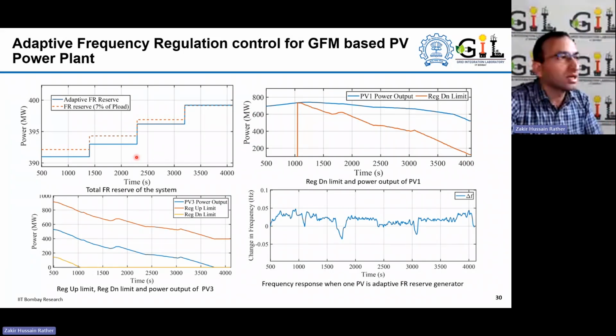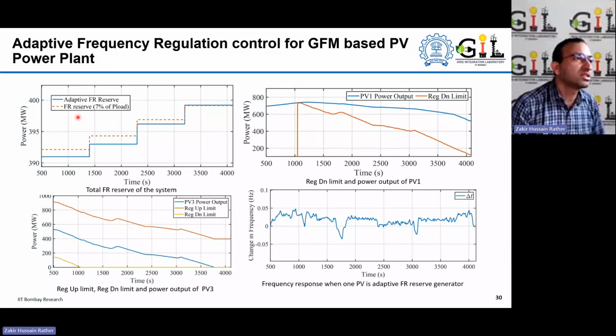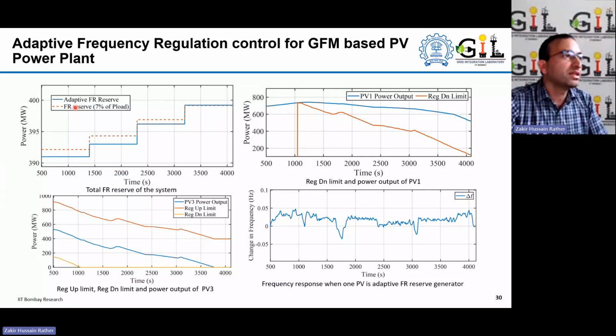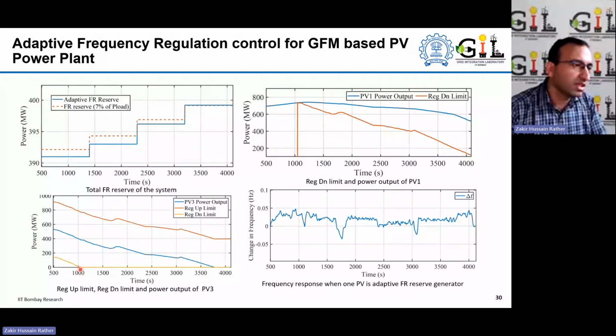So what we did is we considered that 7% of the load should be the reserve. As a simple dimensioning of the reserve, we considered that 7% of the load equivalent has to be the reserve from the solar power plants. And then what we proposed is adaptive frequency regulation and reserve maintenance in the system. So you can see here, this is the reserve requirement, and this is the actual reserve maintained in the system from these power plants. The first one is power plant 3, which is keeping the reserve. We have considered a symmetric reserve requirement, 7% up reserve and 7% down reserve. And you can see here, until this 1000 seconds, this plant is maintaining the up reserve and the down reserve in the system.